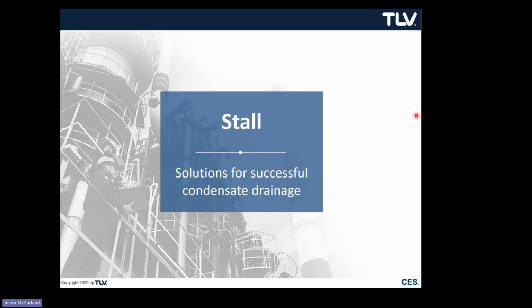The problem is that the extra oversurfacing beefs up the heater to give it more BTU capability than we need. To counteract that, the control valve has to throttle down and deliver a lower pressure. That's not a problem in and of itself, but it becomes a mismatch with the process heater and the drainage solution. Not considering that scenario, you would think, okay, the steam trap should be just fine, I've got plenty of pressure. But you weren't considering this very high oversurfacing. Now the control valve has to throttle down more than you originally anticipated, and that leads, hypothetically, to a negative differential scenario.